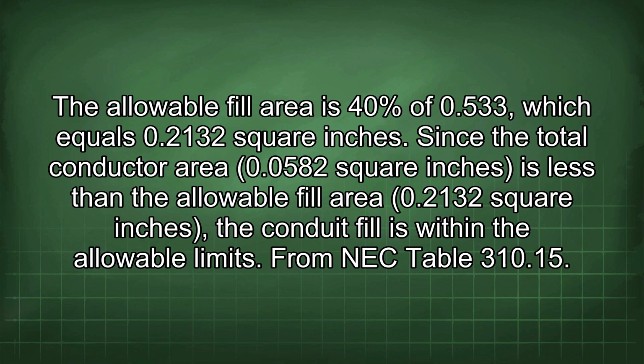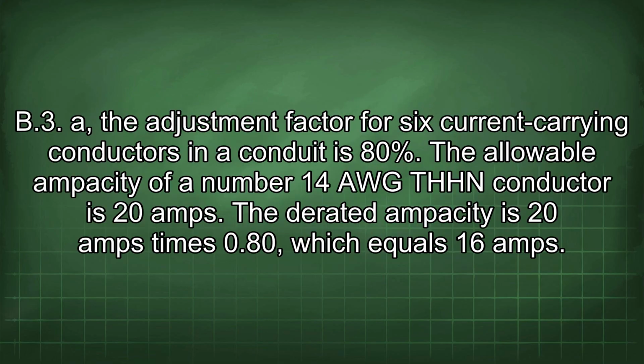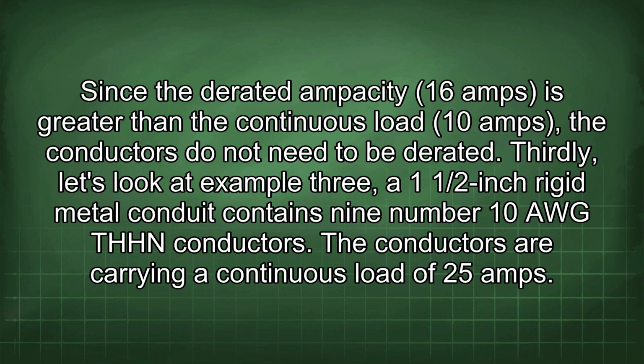From NEC Table 310.15(B)(3)(a). The adjustment factor for 6 current carrying conductors in a conduit is 80%. The allowable ampacity of a number 14 AWG THHN conductor is 20 amps. The derated ampacity is 20 amps times 0.80, which equals 16 amps. Since the derated ampacity 16 amps is greater than the continuous load 10 amps, the conductors do not need to be derated. Thirdly, let's look at example 3.